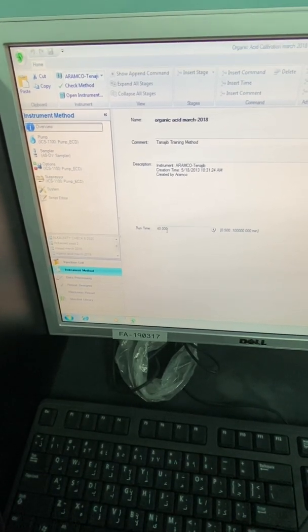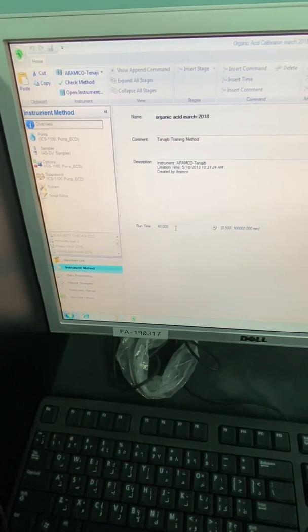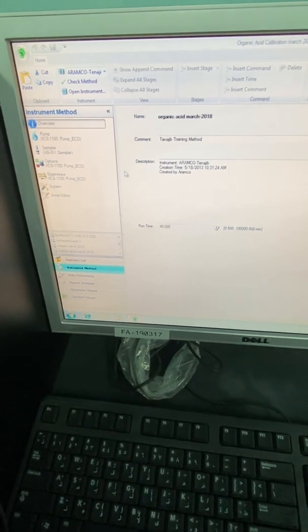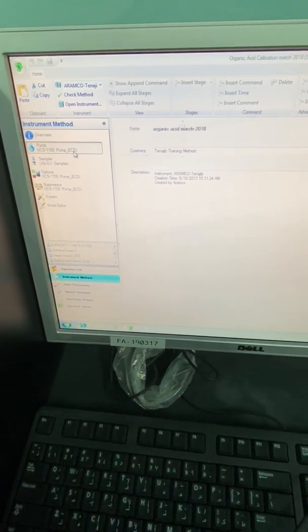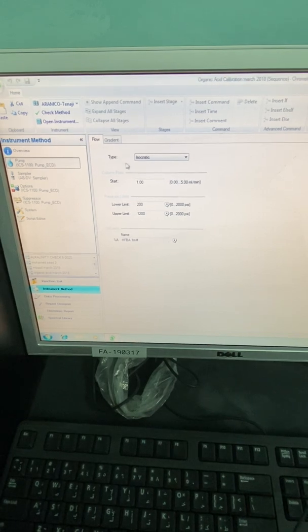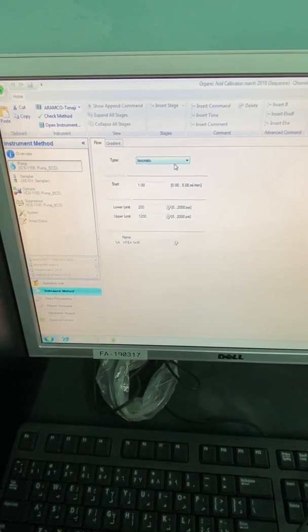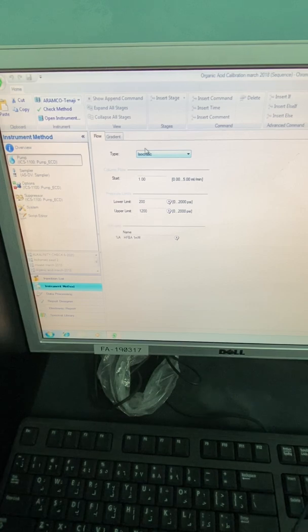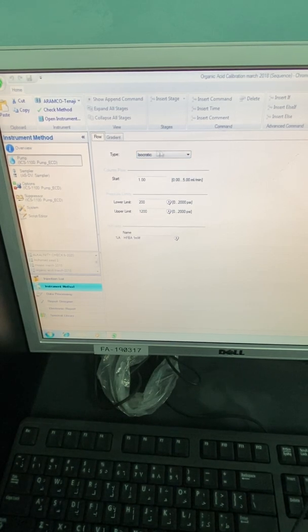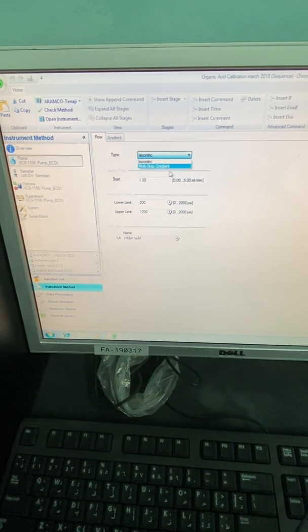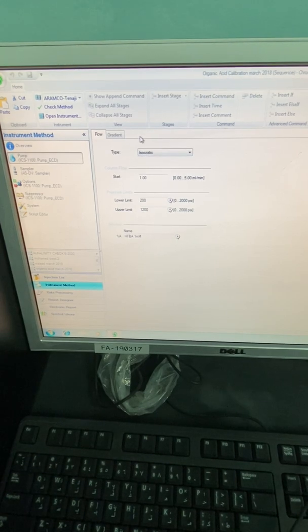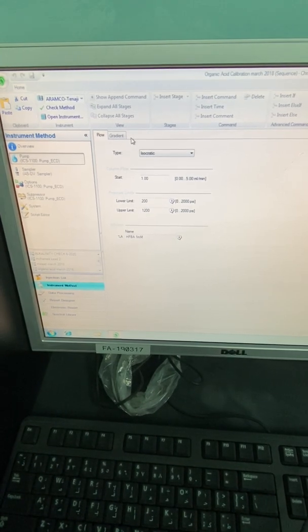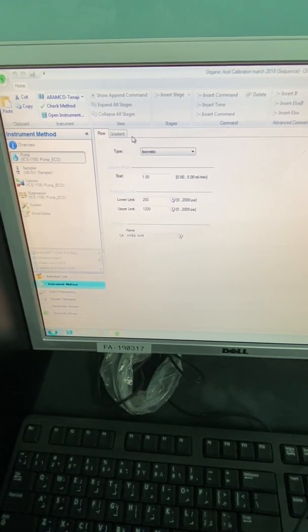You have to mention what is the runtime, 40, 30, 50 based on your application. The pump, this is the pump information. Is it isocratic, which means that the pressure is stable, or you have to graduate the pressure. In this case isocratic. If you make multi-step, you have to mention for each step at which time the pressure or the flow rate of the pump.